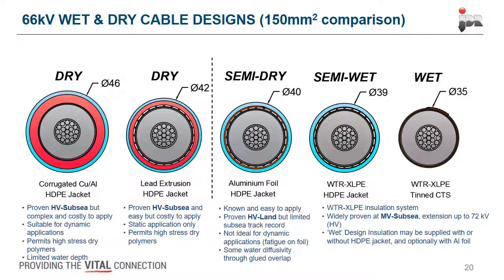So if you looked at a traditional, say, 66 kV cable design used in subsea cables, it would invariably be using a lead extruded design, a dry design of cable. The problem with that is that lead is not a good material for any dynamic or fatigue application. So there have been a couple, and only a couple, of higher voltage cables that have been dynamic in the offshore sector, which NKT, or ABB as it was, provided, where they used a corrugated copper layer to keep the insulation system dry, and then avoided the need of lead for that high fatigue environment. Now that's a good solution, but it's also an expensive solution per meter.